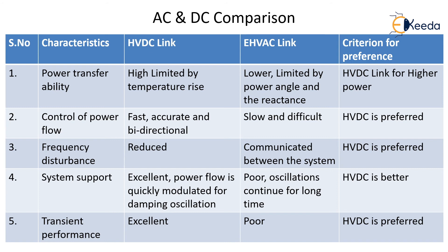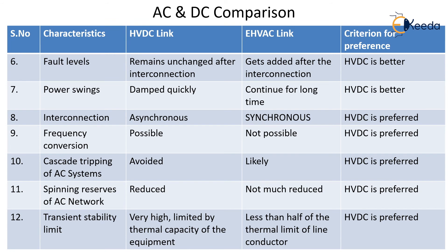For transient performance, HVDC links work effectively and are excellent, while EHVAC is poor. If a system is highly prone to transients, HVDC should be preferred. For fault levels, HVDC link fault levels remain unchanged after interconnection, whereas with EHVAC the fault level gets added up after interconnection — so HVDC is again better. For power swings, HVDC damps them out quickly, while in EHVAC power swings continue for a longer time — again favouring HVDC.